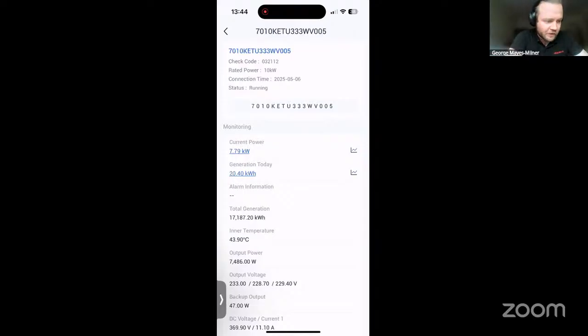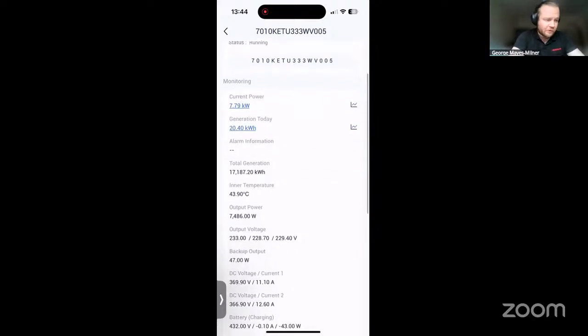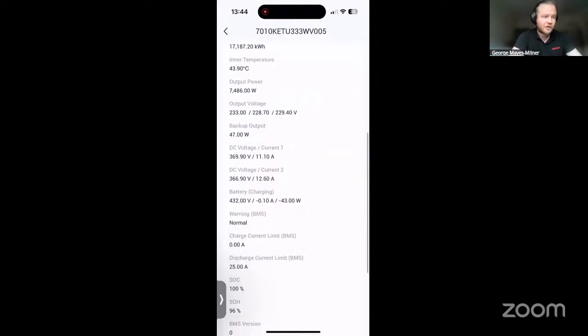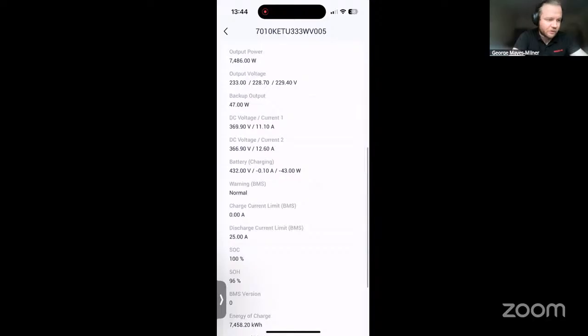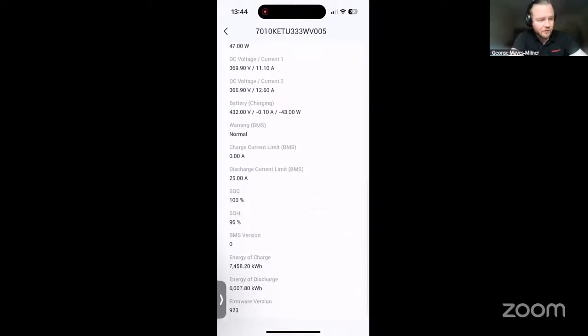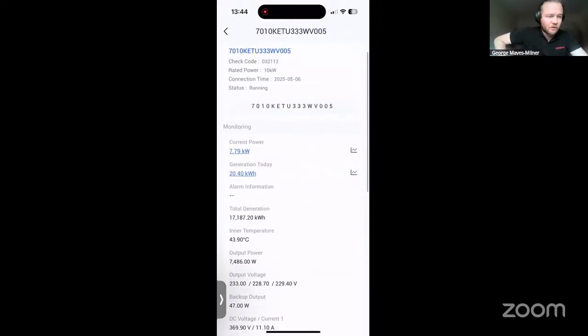You get to see a bit more in-depth information into what the inverter is doing: total generation, the inner temperature, output power currently, which will match what we were seeing on the flow chart earlier, the output voltage on each phase, and the DC voltages and currents, the battery voltage, everything there, whether there's any warnings on the BMS, the state of health of the battery, the state of charge of the battery. And if you're an installer and you're on this page, you'll also have access to some monitoring controls for remote control of the battery, things like setting time of use charges and stuff. But that's a separate webinar, that one.